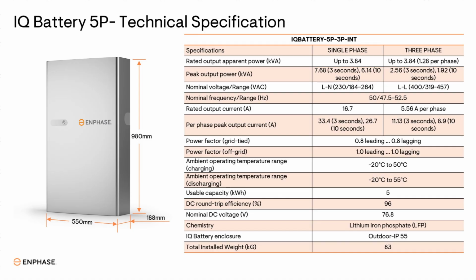DC round trip efficiency is 96%. The nominal DC voltage is 76.8 volt, below 80 volt. With low DC, you are not able to access this DC voltage. This is packed inside the battery, so you are only going to get AC. The chemistry is lithium iron phosphate, the safest in the industry, and the IQ battery enclosure is IP55. Total weight of the battery is 83 kgs, including the back plate, the battery, the cover, all the things. So it's a wall-mounted battery also.